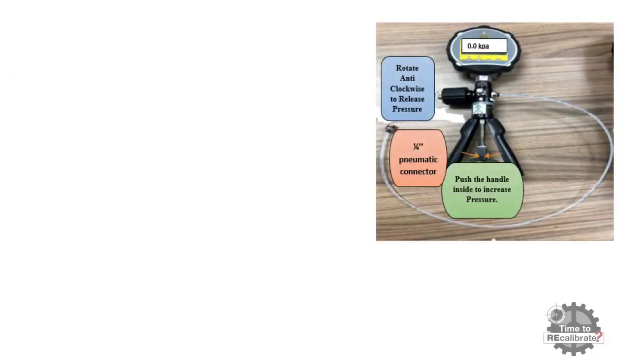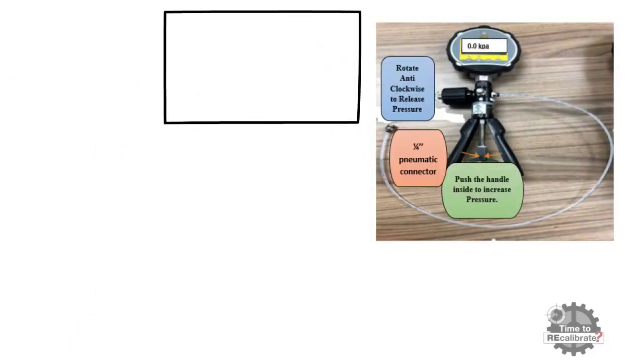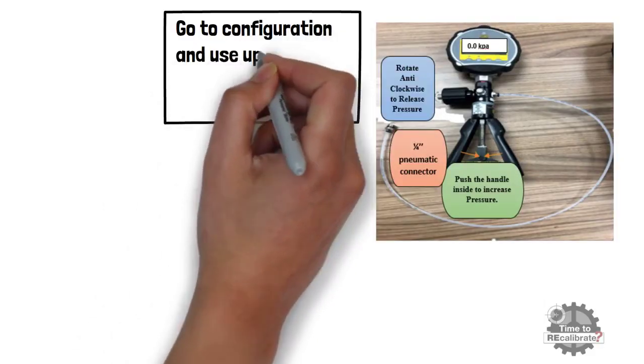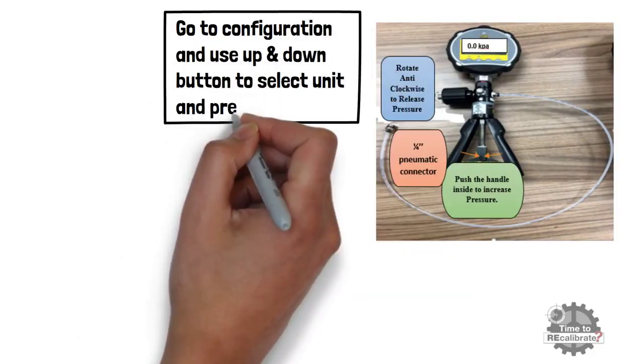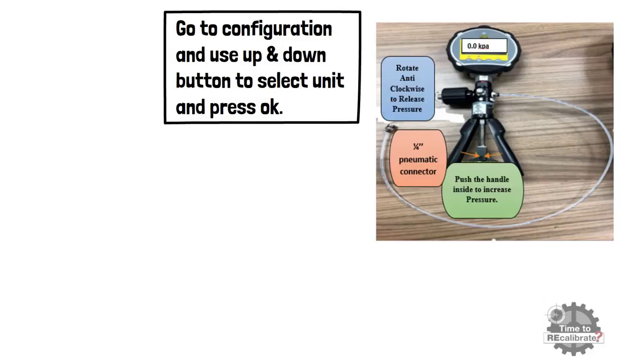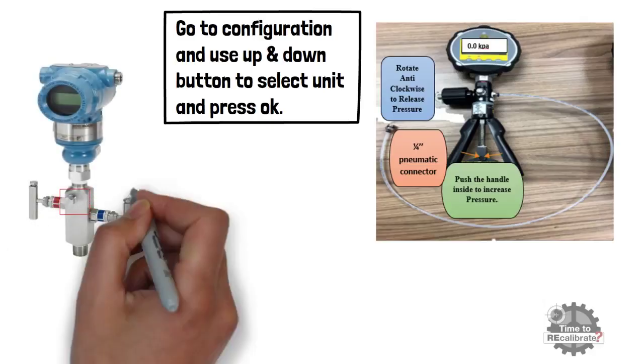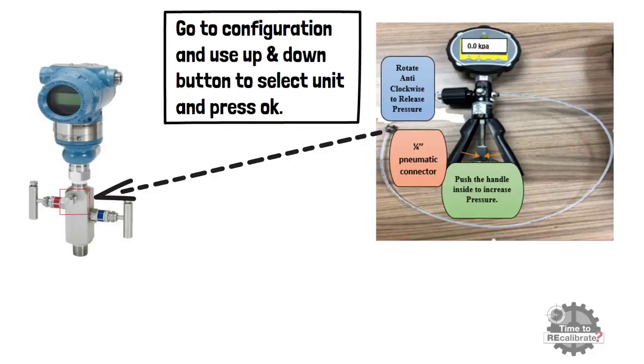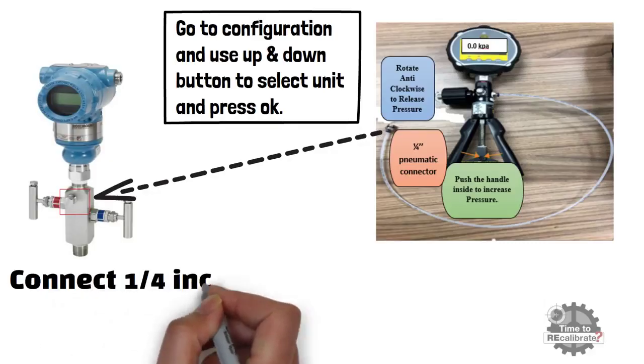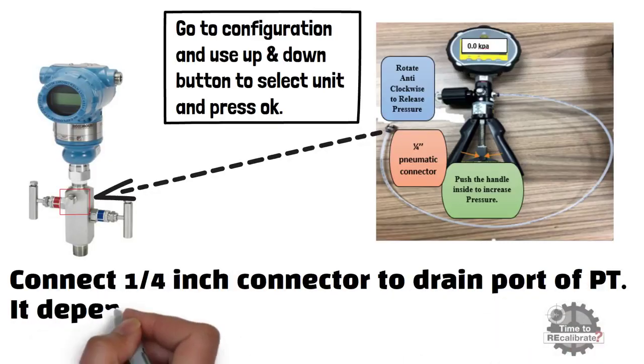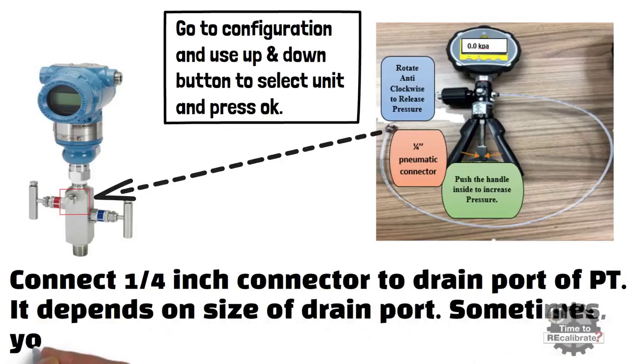In order to set the unit in the pressure calibrator, go to Configuration menu and use up and down button to select unit, and press OK to confirm selection. For example, if you want to set kPa unit, go to Configuration menu and use down button until you see kPa. After this, press OK to confirm selection. Now, connect a 1/4 inch connector to the drain port of pressure transmitter. It depends on the size of the drain port. Sometimes, you may need a 1/2 inch connector.